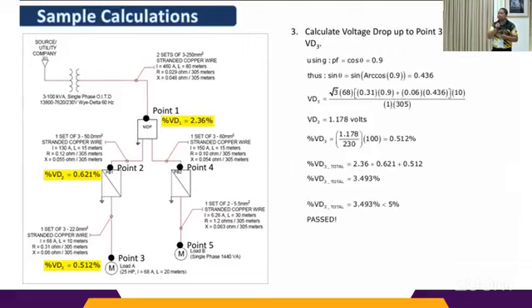Okay, next. Step 3, calculate the voltage drop up to Point 3, VD3. Again we use the formula, but the power factor now is 0.9: square root of 3, 68, 0.31, then 0.9, and so on. Voltage drop 3 is 1.178 volts, so the percent voltage drop is 0.512%. For the total, 2.36 plus 0.621 plus 0.512 gives 3.493%. The total voltage drop is less than 5%, so we passed.